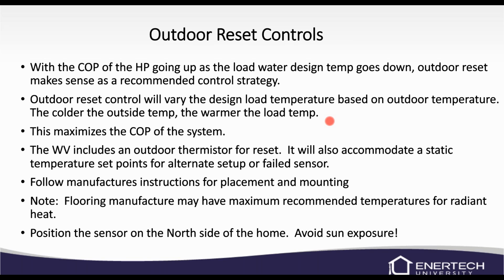Again, we do include the outdoor thermistor. If for some reason you can't get that installed right away, or it's broken or something like that, we can do a static temperature set point if the sensor has failed. We can go into the settings and do that. Obviously, follow the manufacturer instructions for placement and mounting. We basically just want to position the sensor on the north side of the home and avoid sun exposure.